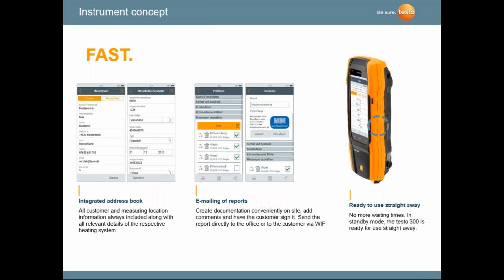Again, it not only has the capability of seeing everything simultaneously, but it also has the capability of storing all that information simultaneously. So we can store thousands and thousands of tests internally in the instrument if we want to. We can store a detailed description of the customer, a detailed description of the measurement itself and where that measurement is being taken, whether it's a number 2 boiler or it's a job number. We have a lot of information that we're storing in this instrument, including the measurements that we're getting.